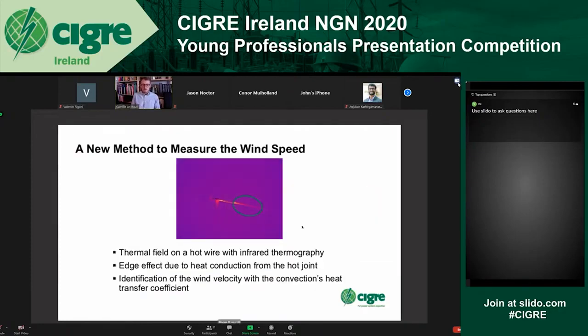This leads to lots of false positives due to the uncertainty in the wind velocity given by the pilot. This is why we need a new method to measure wind speed. With an infrared camera, we can measure the thermal field on the joint—this is what we need—but we can also measure it along the conductor. Inside the green circle, you can see the temperature is not uniform; this is because there's an edge effect due to heat conduction from the hot joint. We can identify the wind velocity using the convection heat transfer coefficient that is hidden in this heterogeneity inside the green circle.